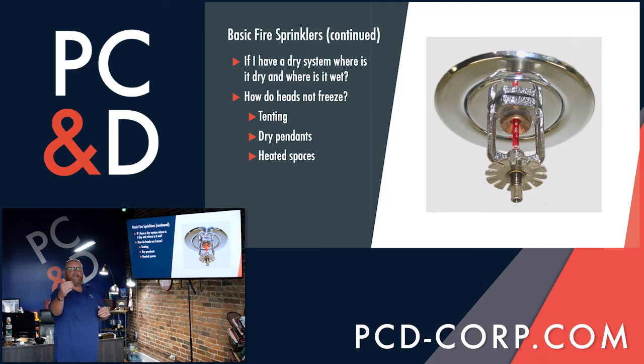So if you knew why it was so important to drain your low point valves, now all of a sudden it makes sense. Oh, I don't want a sprinkler to bust at midnight on Christmas and I've got to spend Christmas Day in the facility because the sprinkler line's busted. No, let's do our PMs and we can try to avoid that.